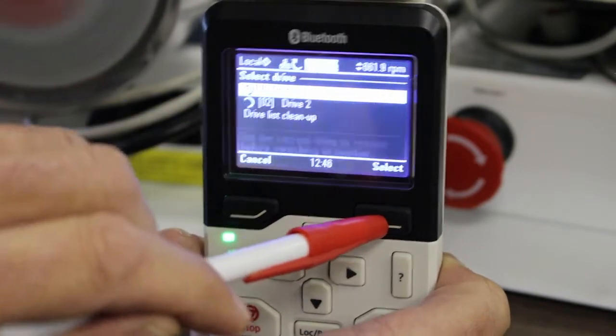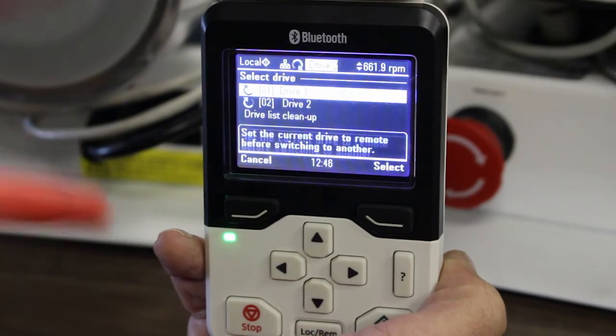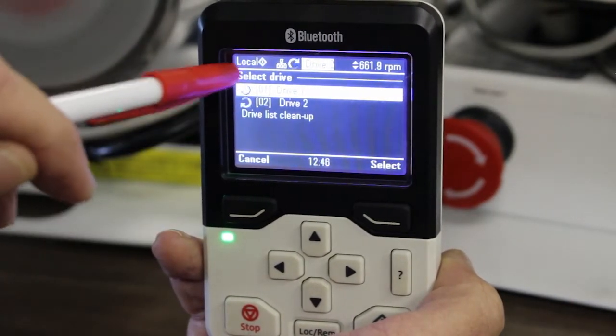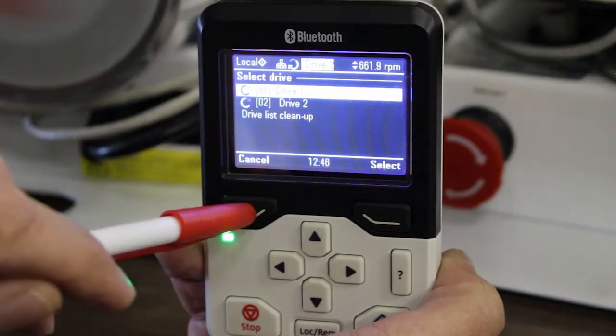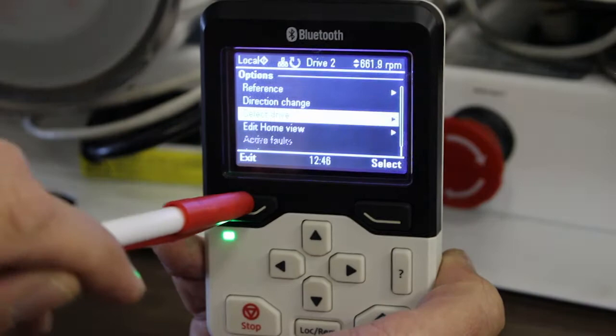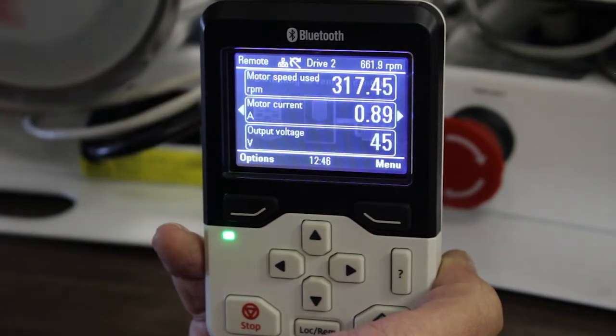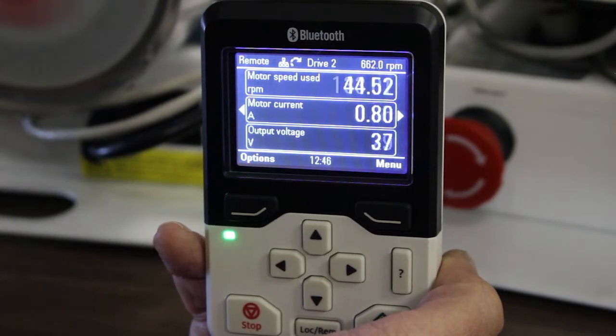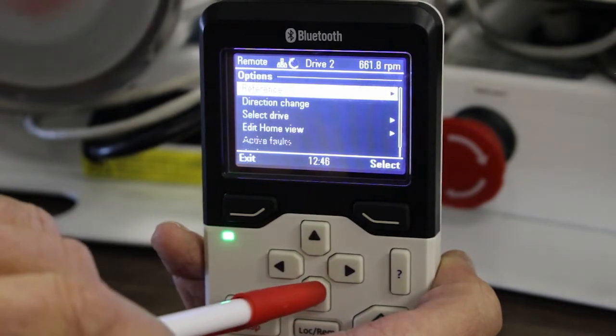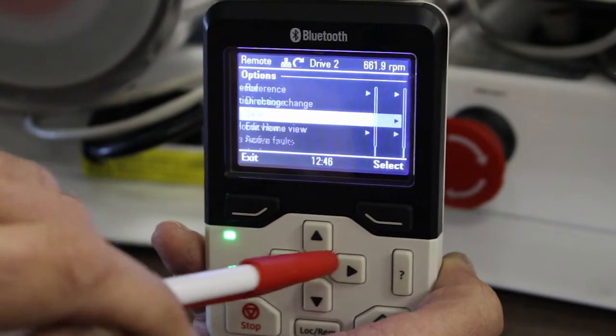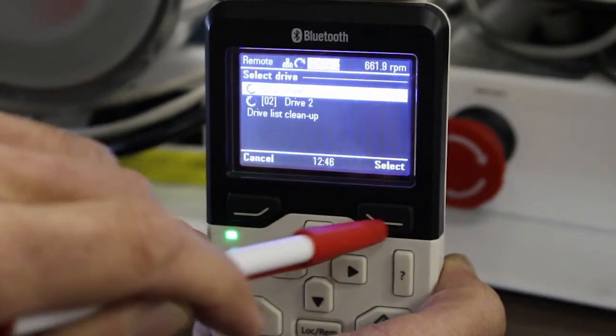It won't allow you to go to a different drive if you are still in local control mode on the current drive. So what you have to do is switch back to remote first. Drive 2 is now in remote — I can start it in remote — and now I can go to Drive 1.